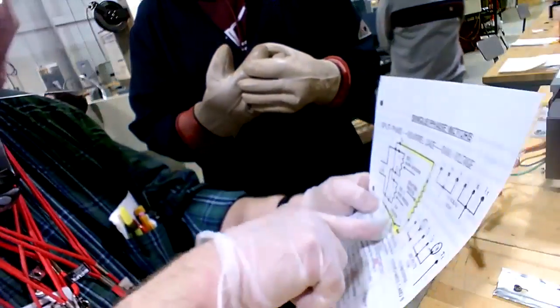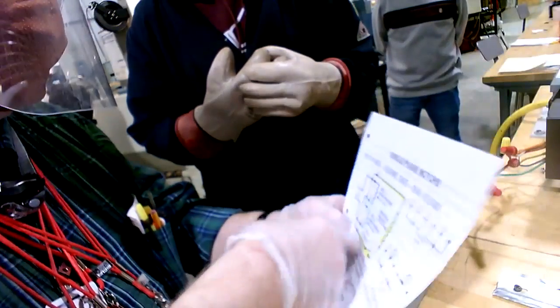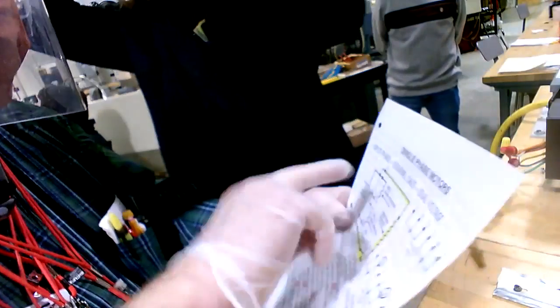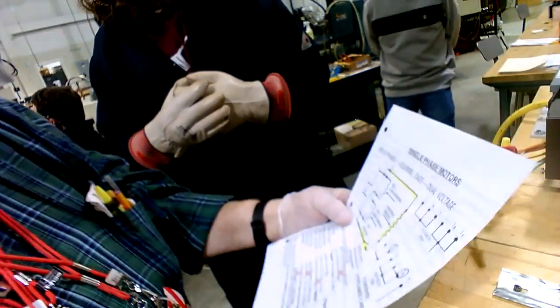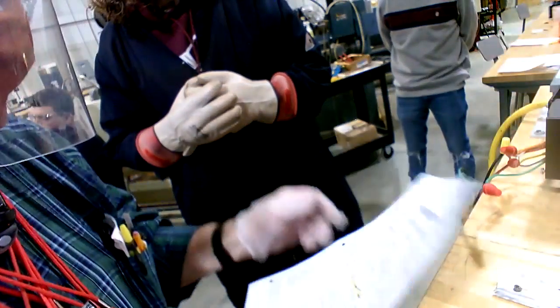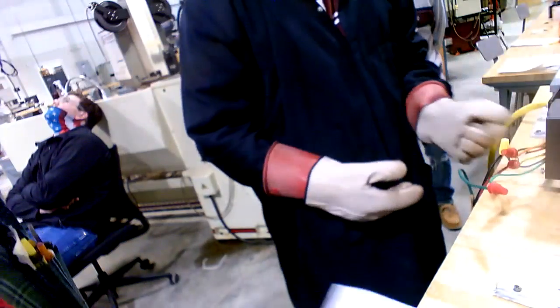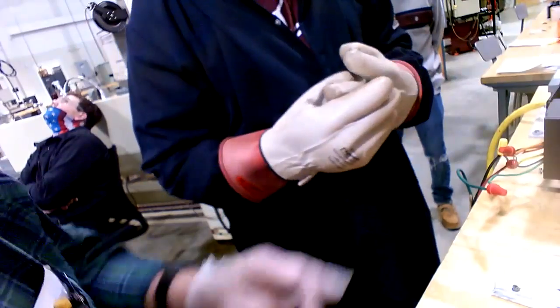You're changing the start line. On this one, the black and red is the outside leads, and you're flipping the start line without flipping the main run line. Okay? And that has to do with that start capacitor and that centrifugal switch. When it starts out, that switch is closed, and that start capacitor gives the start line a boost. And when you flip the black and the red leads, it changes the polarity of that winding. Exactly, yeah.